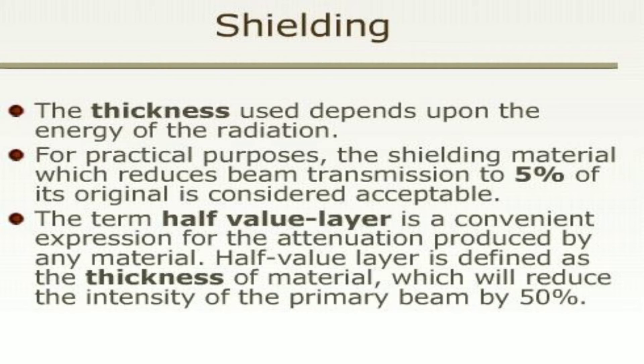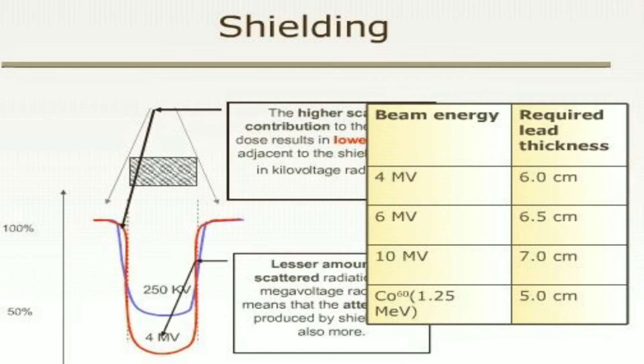Half value layer is defined as the thickness of material which will reduce the intensity of the primary beam by 50%. For 4 MV beam energy, required lead thickness is 6 cm. For 6 MV beam energy, required lead thickness is 6.5 cm. For 10 MV beam energy, required lead thickness is 7 cm, and for Cobalt-60 having average energy 1.25 MeV, the required lead thickness is 5 cm.